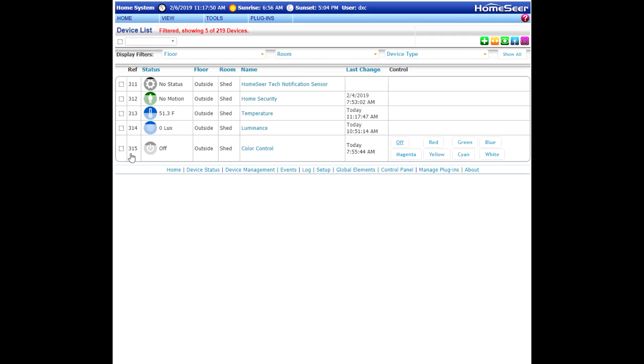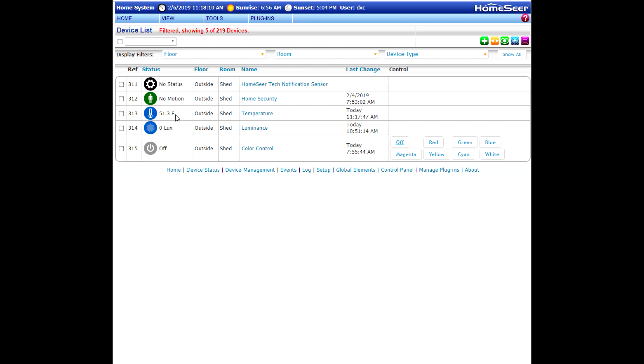Okay. So the uncalibrated temperature reading is 51.3 degrees. Quick calculation of that. 51.3 minus 46 is 5.3 degrees. Again, we need to enter in a value that is 10 times larger than that. But we need to do it in the right direction. I'm subtracting 5.3 degrees. So I want to put in a value of minus 53.